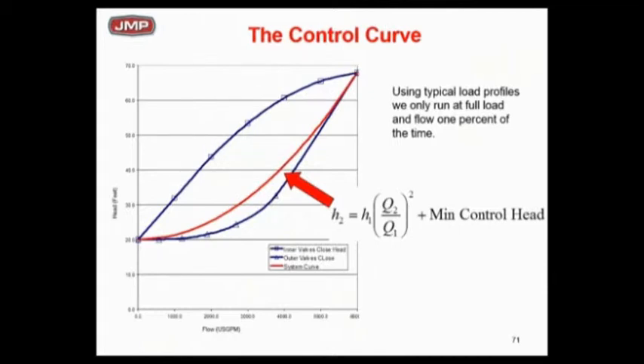In other words, the lower blue line would be the two-way valves closest to the pump. The higher blue line would be the two-way valves furthest from the pump. Control head in this case is 20 feet. It's shut off. But here's the message again.